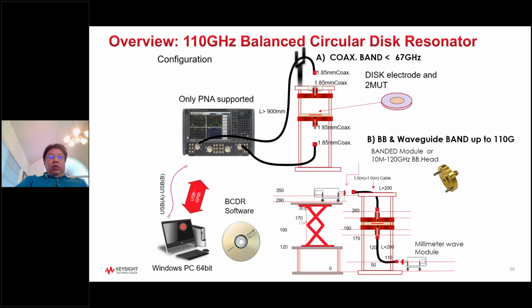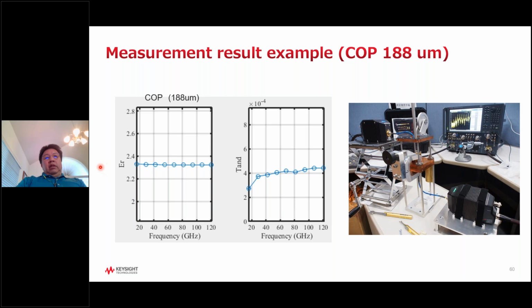Okay, and of course the software runs on the external PC or inside the network analyzer. So some examples using the COP 188 microns. You can see here the first resonant frequency is 20 gigahertz. This is the real part of your permittivity, or your Dk value. And next will be 40, 60, 80, 100, 120 gigahertz. And this is your loss tangent, your tan delta.